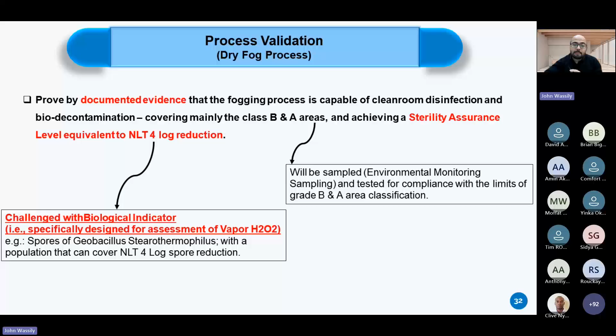Here is a quick overview of how the dry fog process takes place. It involves a portable fogger device or tank and a compressed air source. In this tank we put the sterilant solution, a mixture of peracetic acid and hydrogen peroxide, aimed at decontaminating grade B and A areas because it's effective against all forms of microorganisms, including bacteria, spores, and viruses. Using the compressed air, we spray and fog the sterilant solution present inside the tank through a head constituted of nozzles.